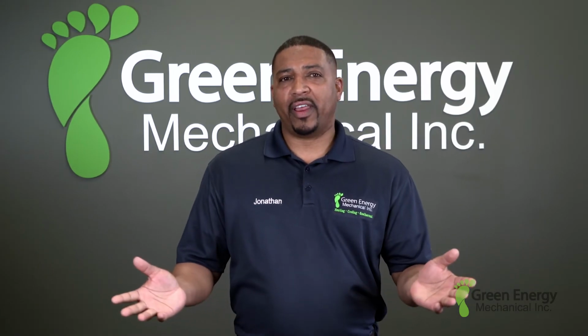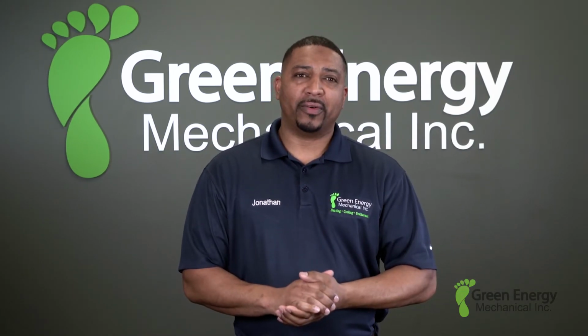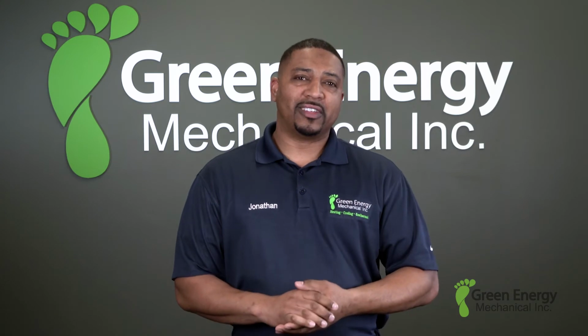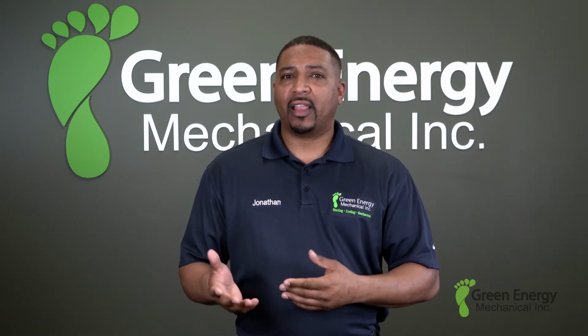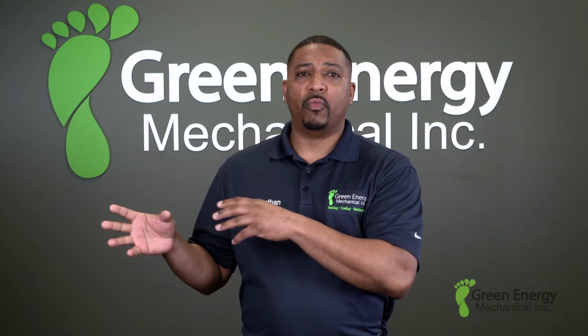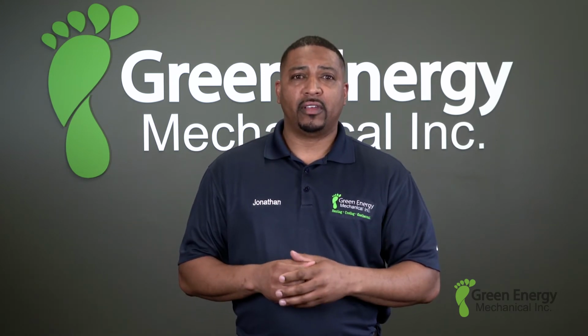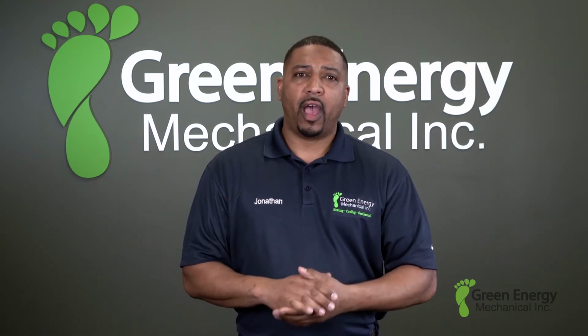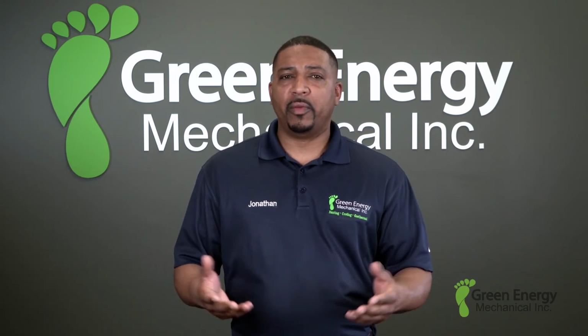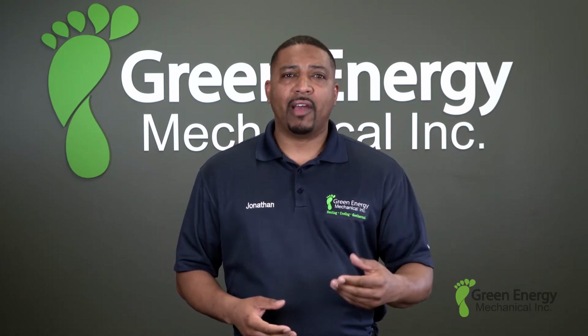So what's it like upgrading your heat pump with Green Energy Mechanical? Well, let me walk you through a recent customer experience. We had a client that had another contractor remove an oil-fired hot air furnace and install a heat pump system. However, the new system would not keep up with the colder weather, and it kept showing errors on their thermostat. After many months of frustration, they called Green Energy Mechanical. We quickly determined that the heat pump was not adequate for their home and would not even have enough heating capacity to keep the home warm in colder temperatures.